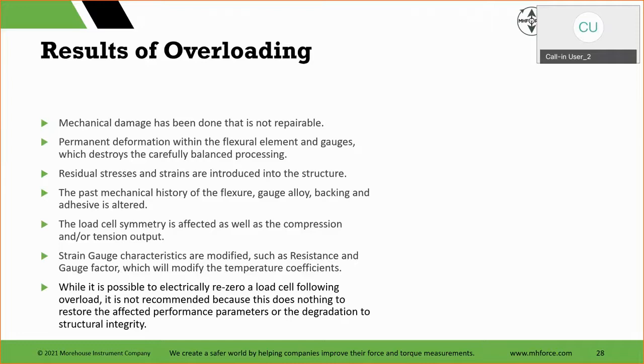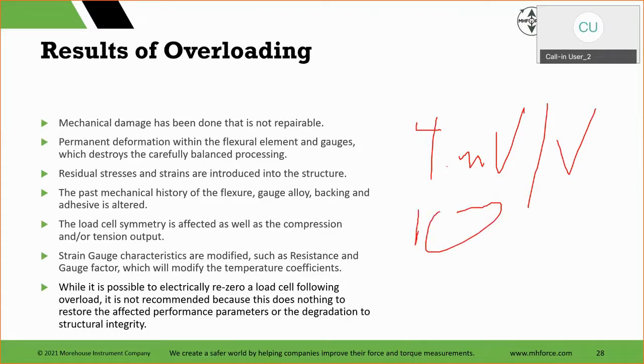The past mechanical history of the flexure, gauge alloy, and adhesive is altered. The load cell symmetry is affected, as well as compression and/or tension output. When we say symmetry, that's compression and tension, which means, if prior to my overload my load cell was reading 4 millivolts per volt, or, say it was reading 10, let's say that equates to 10,000. Sorry for my scribble here, I'm using my mouse. Say that equates to 10,000 pounds.